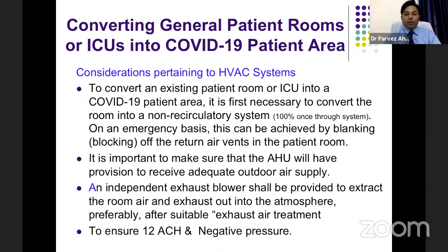Then how to treat the exhaust air from COVID-19 patient areas? There are different methods. HEPA filtration is the most preferable method, which is recommended by ISHRAE. The HEPA filter specification should be a minimum of EN 1822-1 H13 filter class or equivalent. Chemical disinfection can also be done by bubbling the exhaust air through a diffused air aerator tank holding a 1% sodium hypochlorite solution. We have to change it on a frequent basis to maintain its efficacy.